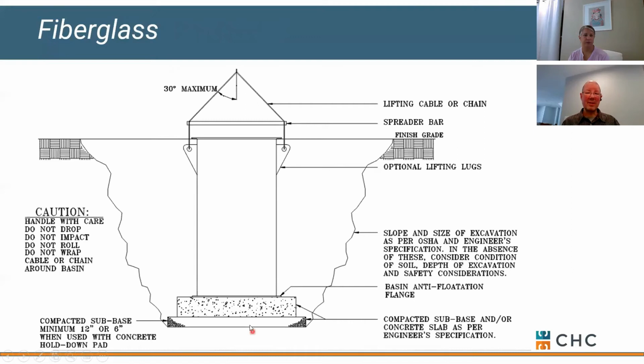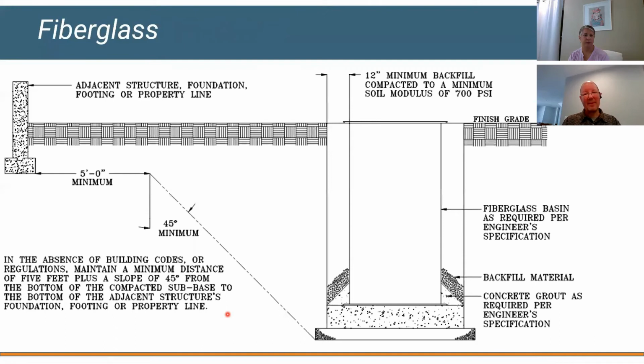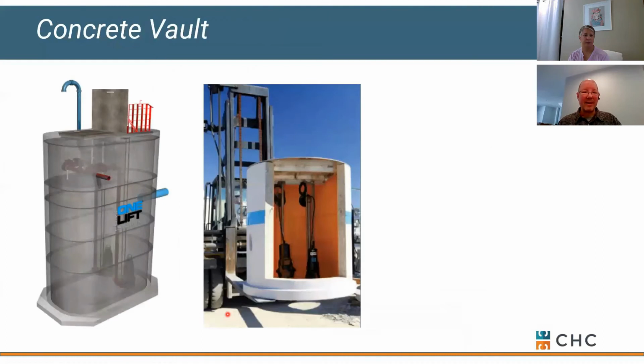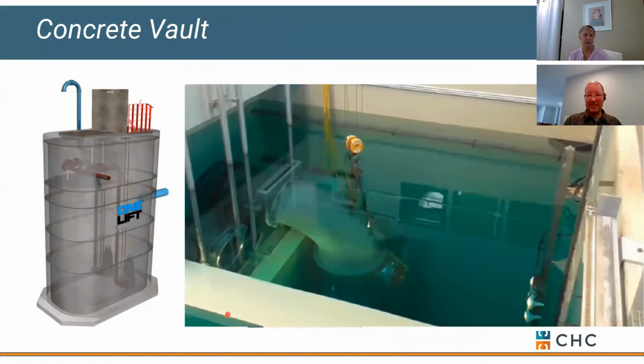One thing to keep in mind: typically you've got some groundwater that's pushing up on the bottom of the basin and trying to push it out of its below grade location. What do you want to call that? Hydrostatic force. It's trying to lift that basin out of the ground like a cork. So to prevent that, you normally install it on some type of housekeeping pad with a compacted base, and then you're also going to backfill it so water doesn't have a chance to come up from underneath and push it out of the ground. A concrete vault is another option. Again, that just is going to get dropped into the space. And I don't know what this install is. Looks like a nuke plant, but okay, now we're talking. That's a pretty cool looking basin.